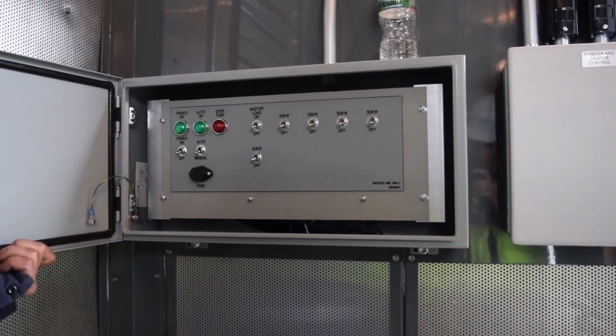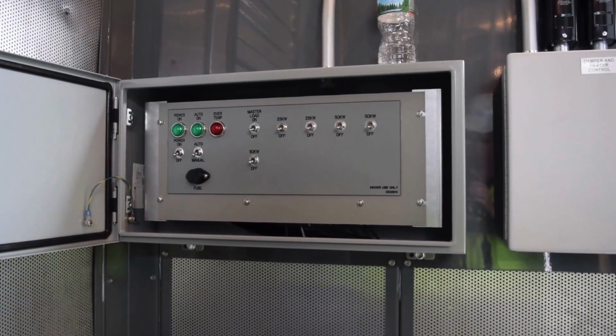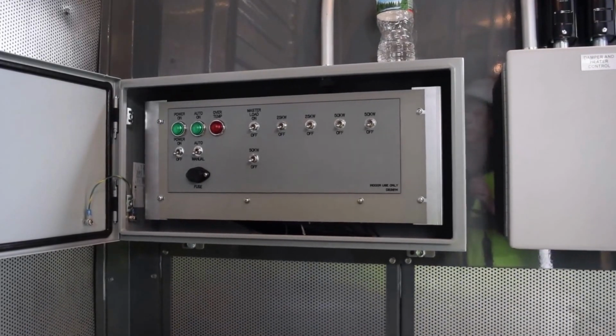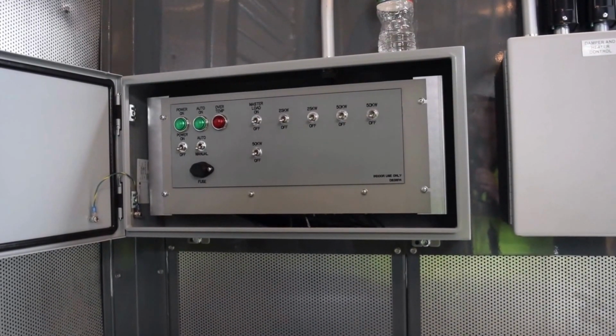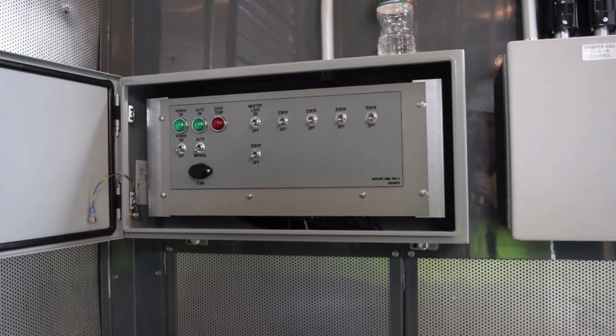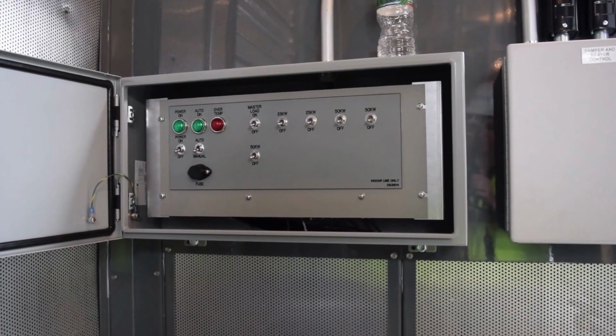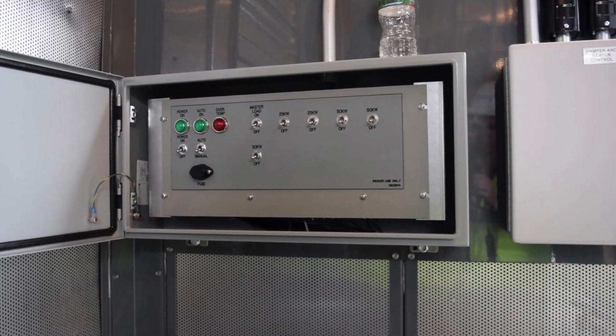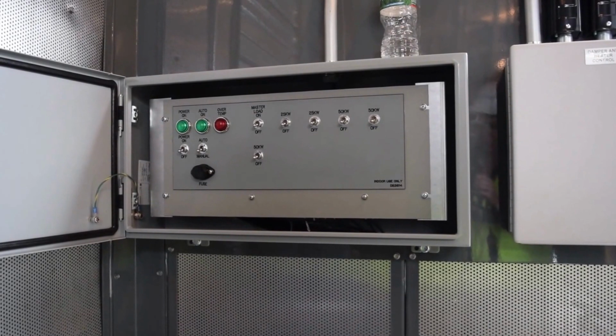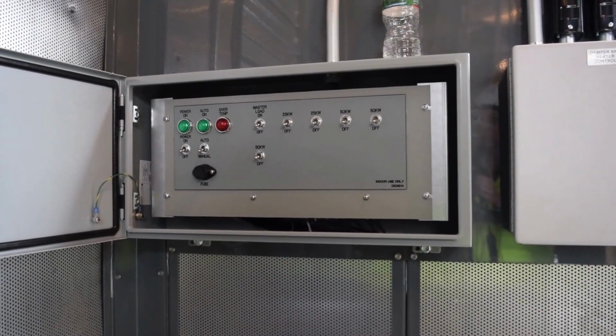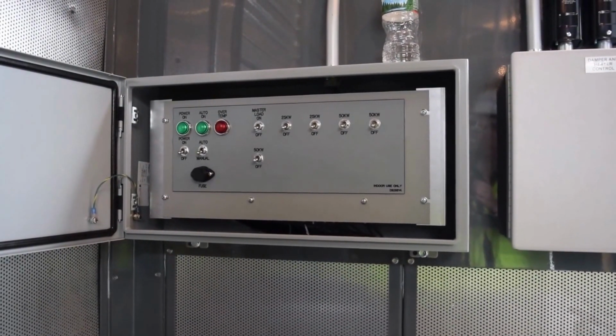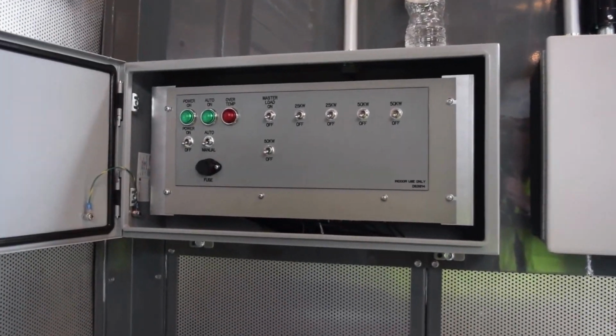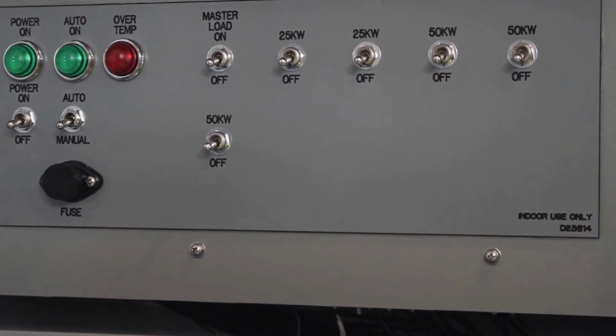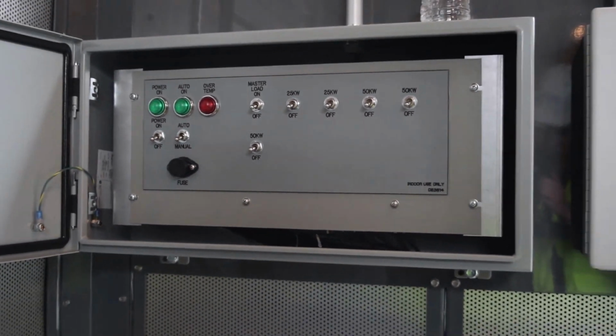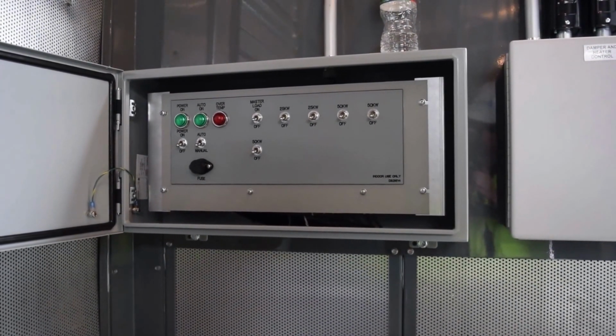So what does this power? Is this all life safety? I don't know the entire layout of your building. Your life safety is on it. I believe your elevator's on it. So it requires 30-day tests. So loaded test every 30 days. So you have to put a load on every time you test run it, or transfer. And I don't do building codes. Okay. Well, no, I know that's the code that has to be done, so I just want to make sure of that.